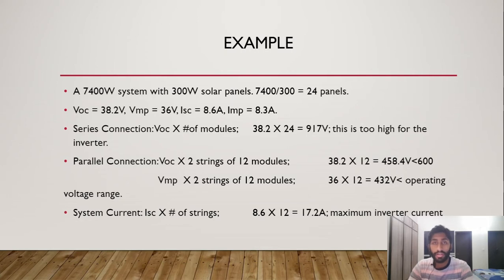You have to mix and match, see what works, what doesn't work, what type of solar system you're looking at - high voltage low current, or suitable high current high voltage. A little bit of mixing and matching, take both into considerations. Calculate for both Voc and Vmp for each string, the Isc as well, and Imp if you want to as well. Imp is the same thing - multiply Imp with the number of strings.